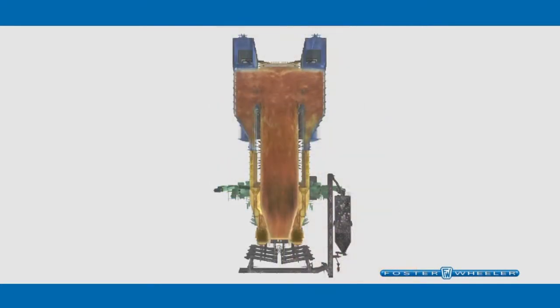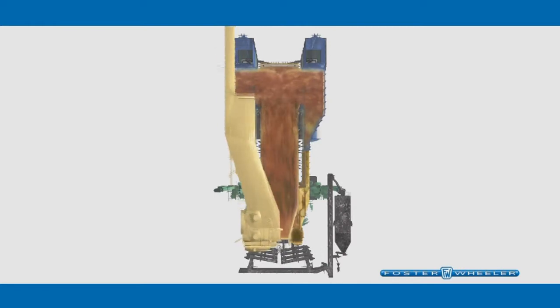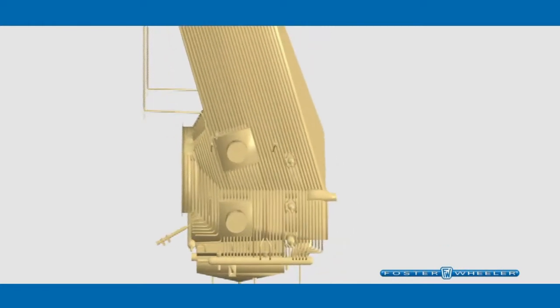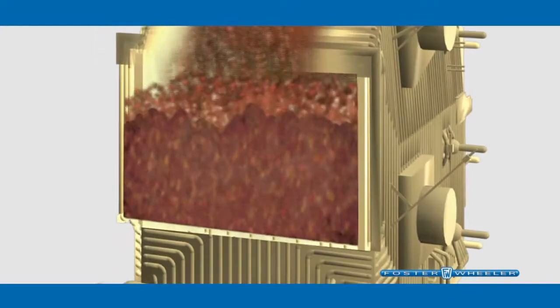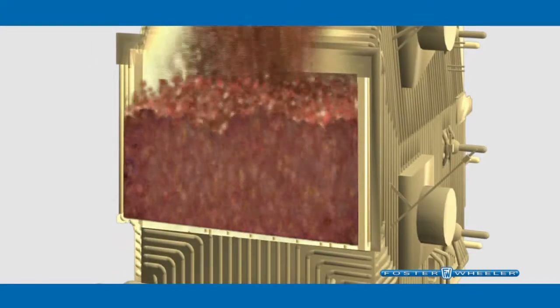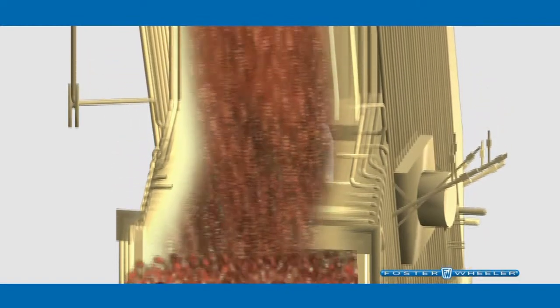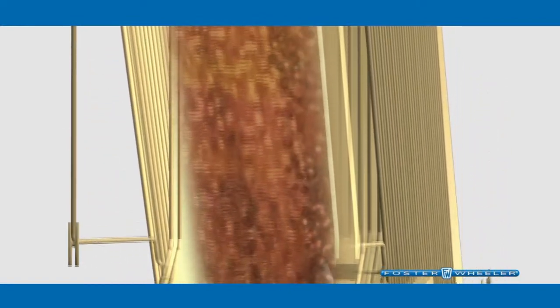Another advanced design feature of Foster Wheeler CFBs is a high performance particle to steam heat exchanger called an Intrex. The Intrex efficiently extracts high temperature heat from the hot particles in the CFB to produce high temperature superheat steam.